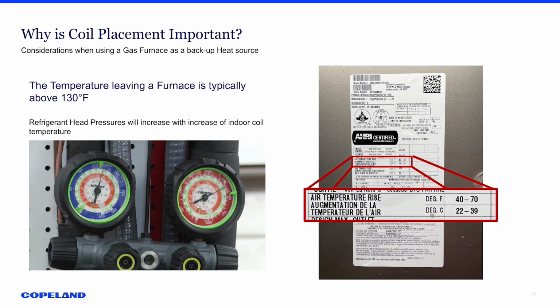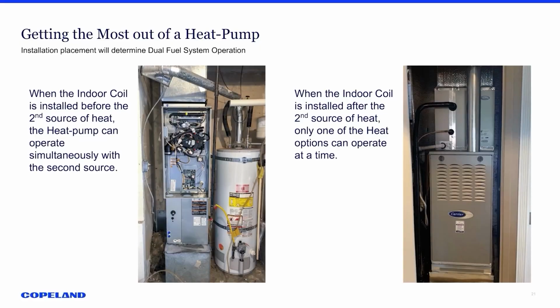And so the placement of a coil when you're doing dual fuel, if you want to run them both at the same time, the coil has to be just like air handler manufacturers are doing, upstream before the fan, before that second stage of heat. That way you are not overheating, or should we say superheating, the refrigerant in that coil as it's going through there. So, the importance of the placement of the coil.